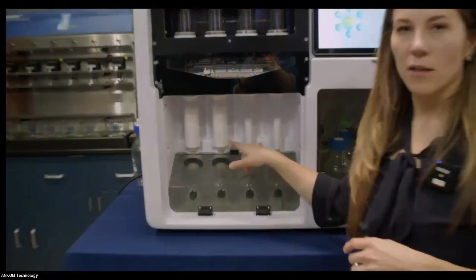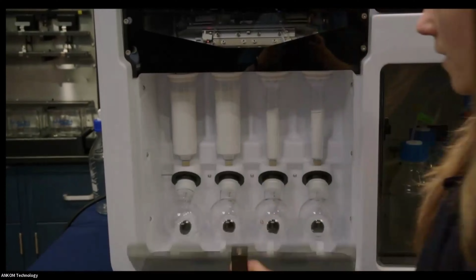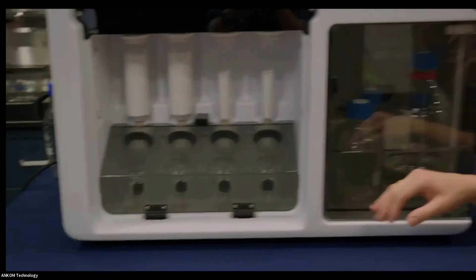The center part here, I have two columns that are shown. The larger column is the vitamin column that is used. This is a one-time use. The smaller column is a total fat column. This is a funnel that's just simply an adapter because of the mouth of where the fluid gets pushed through. These can be reused. The total fat column is a one-time use as well, and they are manufactured by ANKOM. Then down here you have your evaporation chamber and your round bottom flasks where your analyte is then ready for reconstitution or your oil is captured.